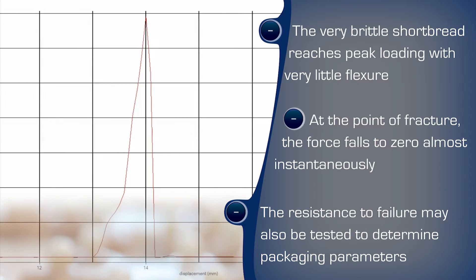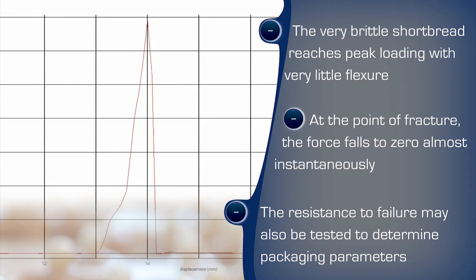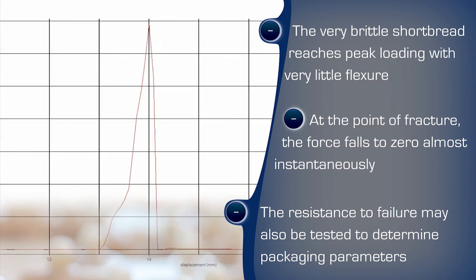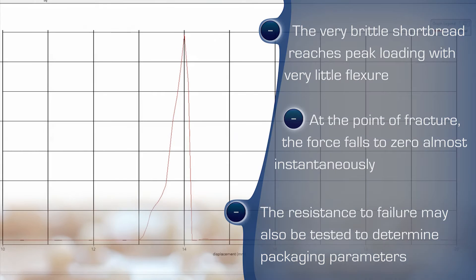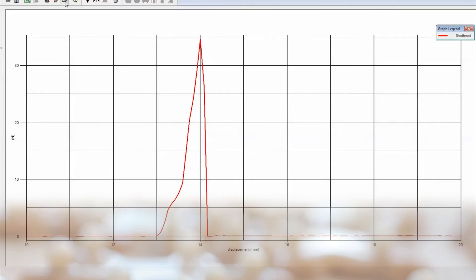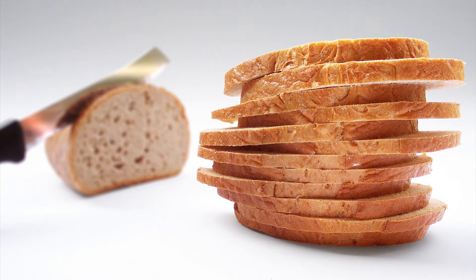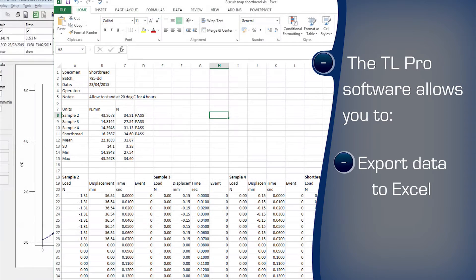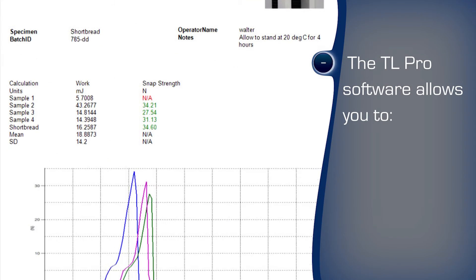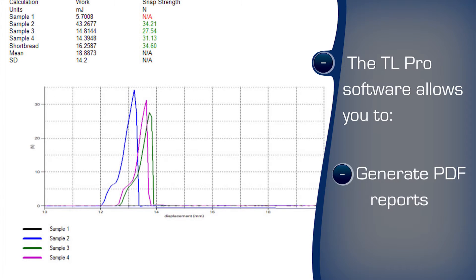For a brittle friable bakery product we would expect a steep rise in compressive force over a very small displacement, followed by a rapid fall off as the sample undergoes a single massive failure. Stale products would undergo some level of flexure and potentially a less instantaneous break. The reversed characteristics would be valuable for products which are desired to exhibit a limited, controlled amount of flexure and which conversely snap when stale. The TL software can export to Excel for further examination and traceability and format the results in a user-customizable report style.